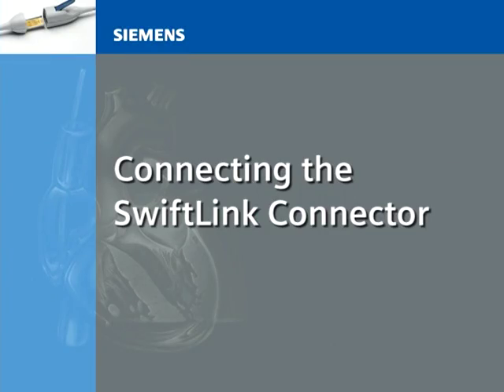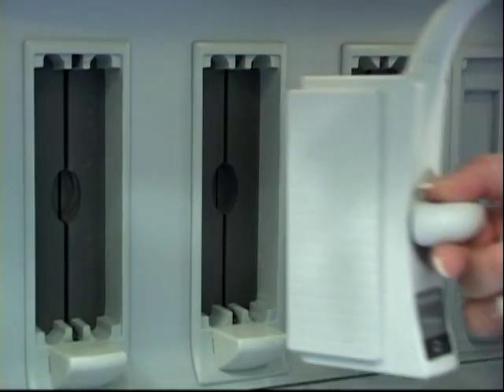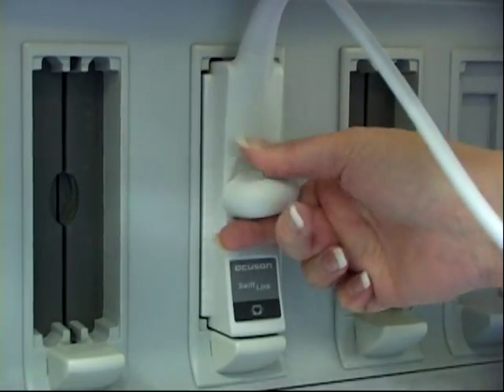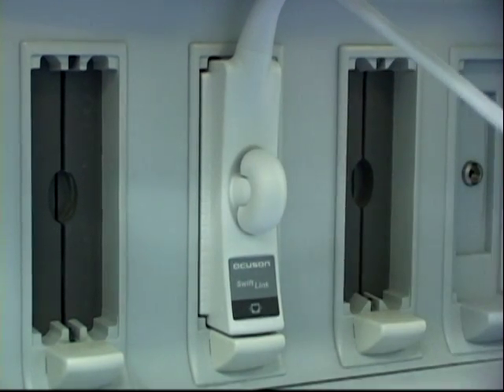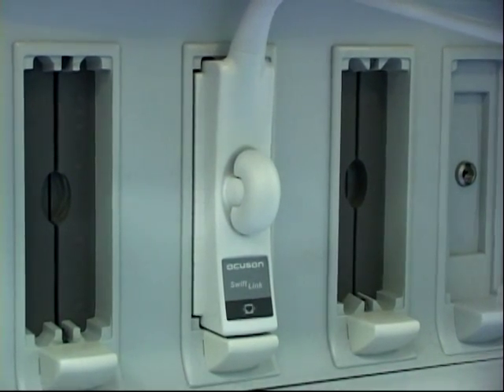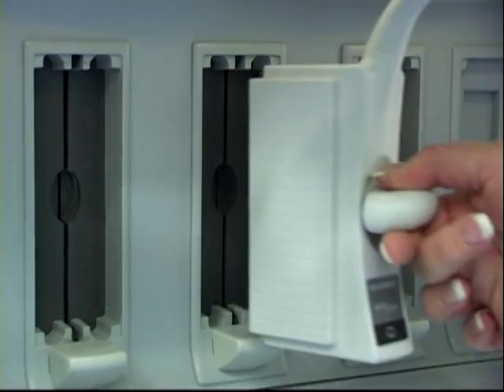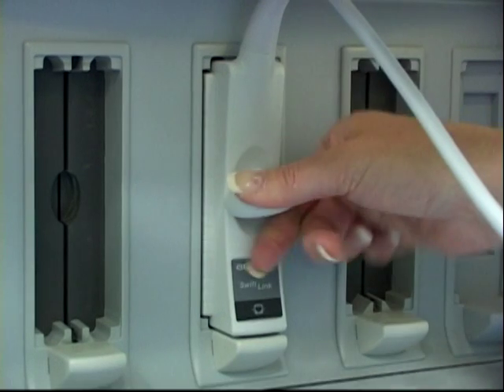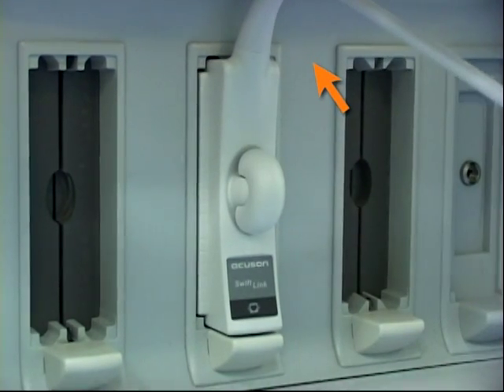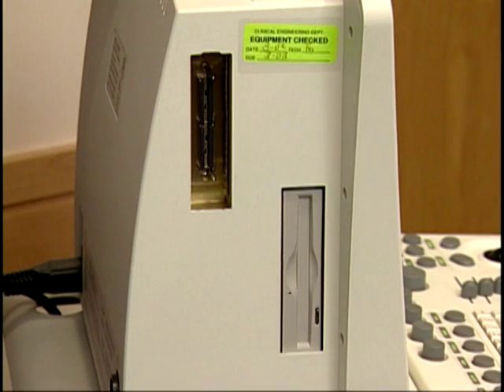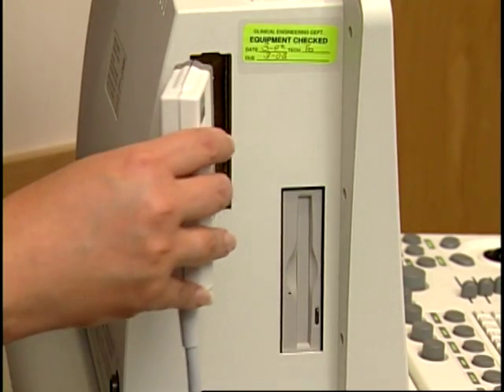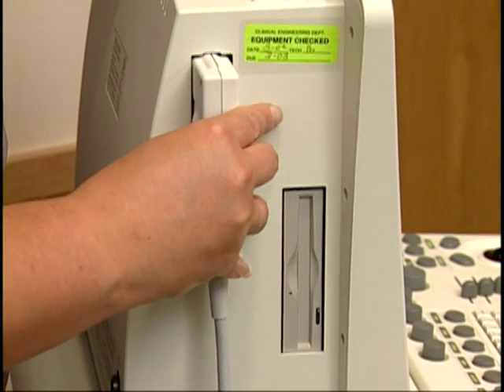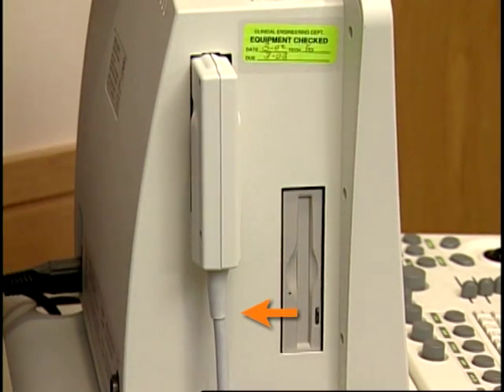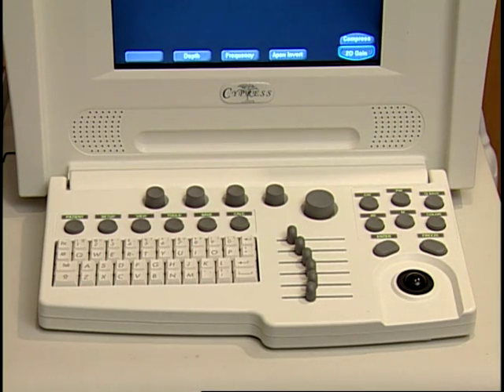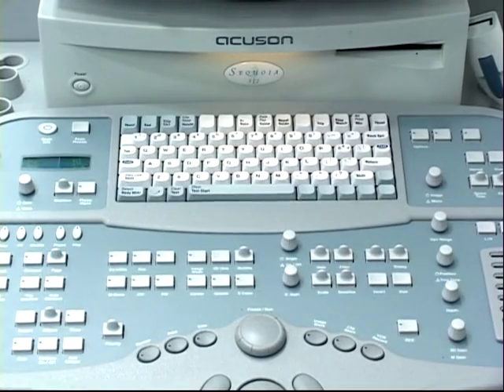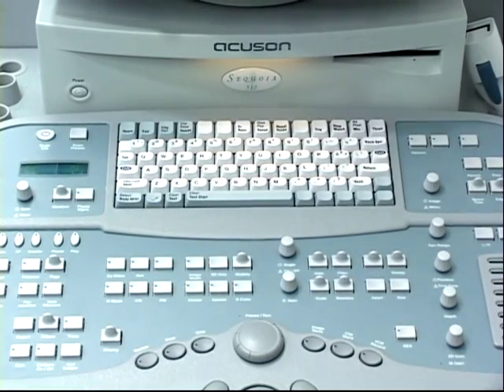Connecting the SwiftLink connector to the ultrasound system. To attach the SwiftLink connector to the ultrasound system, insert the system connector into one of the active transducer ports on the front panel of your ultrasound system. If using an Acuson Aspen or Sequoia ultrasound system, the SwiftLink should be inserted with the cable coming out of the top of the connector. If using an Acuson Cypress ultrasound system, the connector should be inserted into the connector port located on the right-hand side of the system with the cable down. A person outside the sterile field must operate the controls of the ultrasound system unless the system control board is covered with a clear, sterile drape.